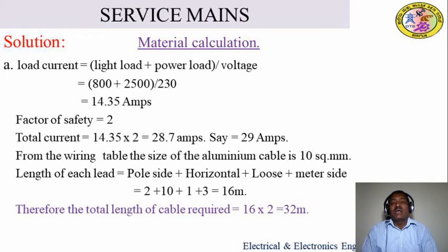If you lay the cable as per the present current rating, then in future as the load increases, the current increases, which generates heat in the cable. When heat is generated, the cable loses its insulation property, or there may be a chance of a fault.